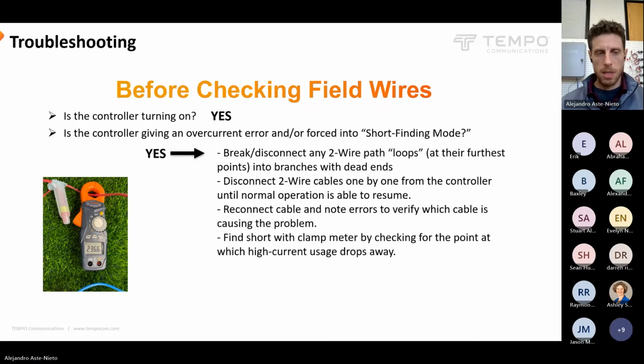And then that typically will mean that there's an overcurrent, there's a short out there. And that's something that we can find with our clamp meter. What we'll want to do is check for where along that wire path the high current will drop away, and it's at that point that the fault occurs. So if we're turning the controller on and it's giving us these overcurrent errors and it's in short finding mode, then we follow those steps.